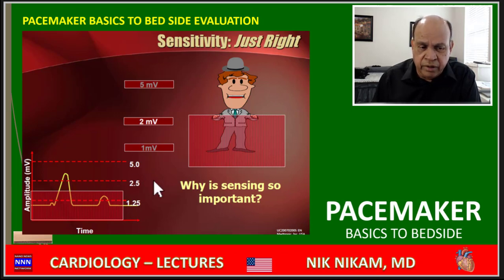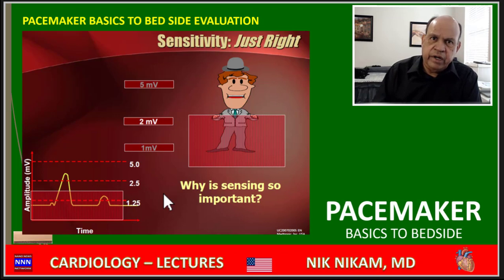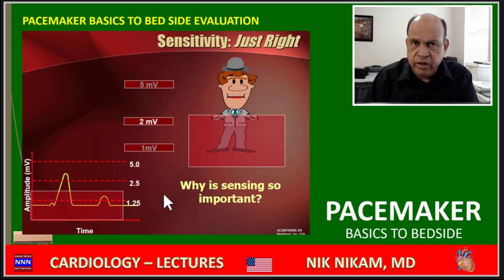In the ventricular electrode, if you set it to like 7.5, it looks for any electrical activity at 7.5. And if it sees that electrical activity, the pacemaker doesn't do any extra work. It lets the human heart continue with the rhythm. So that's the sensitivity part of the pacemaker for atria and the ventricle.